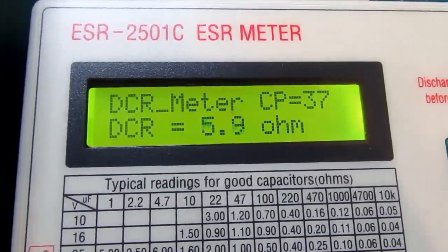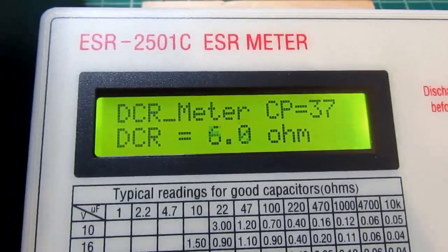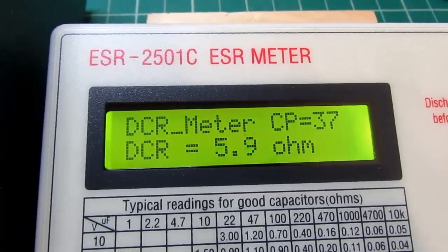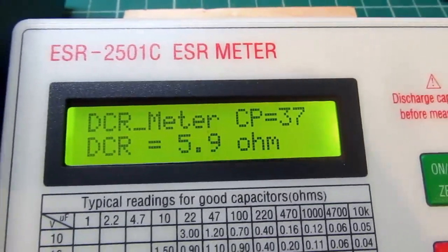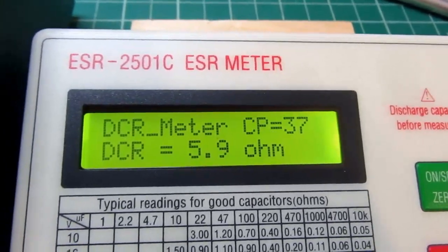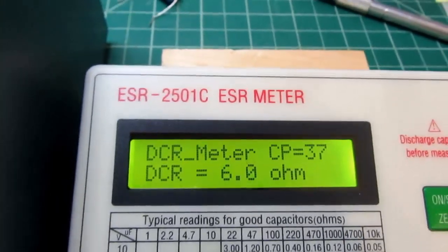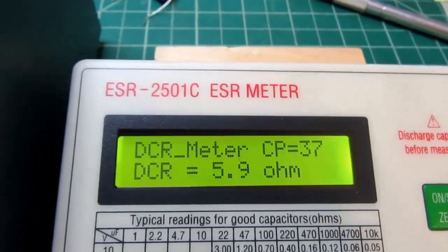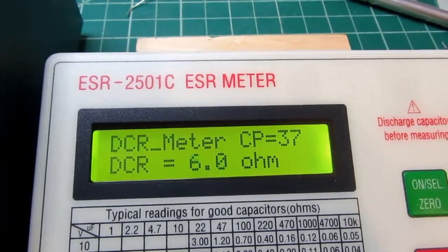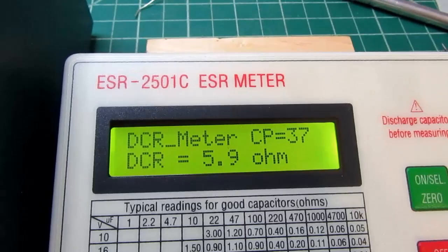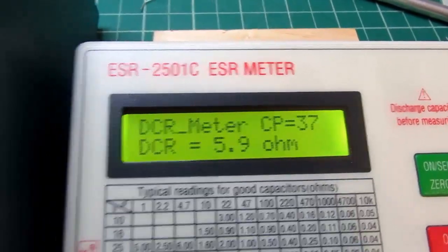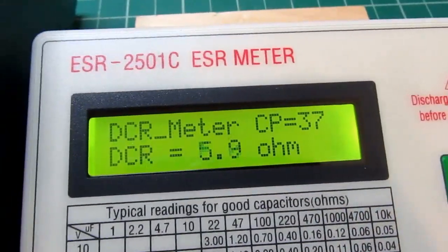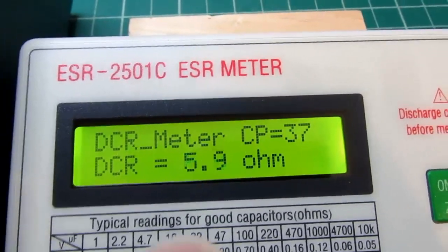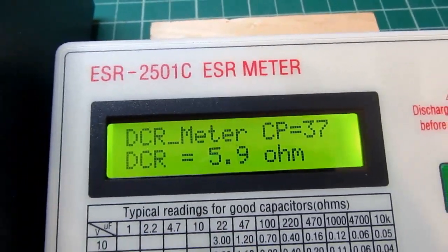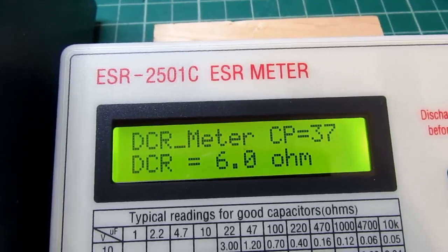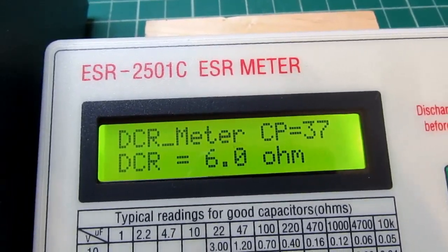It's showing 6 ohms, which is what I've got, but the resolution changed. This meter has 2 ranges: 0 to 5, and 5 to 25 ohms - those are the only resistance ranges it has, everything falls in that range. If it's greater than 25, it just says greater than 25. And of course it can go down into small fractional ohms, which my decade box doesn't do. But I wanted to demonstrate how it shifted gears from one range to the other going from 5 to 6 ohms.